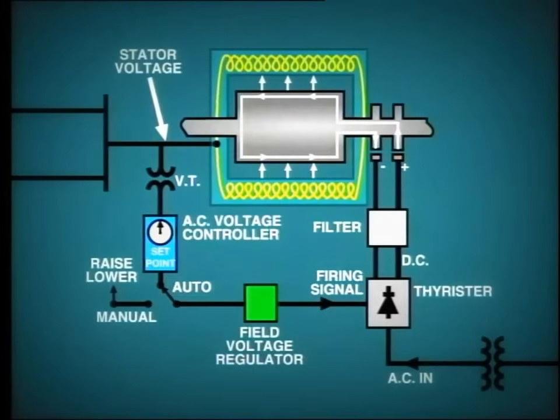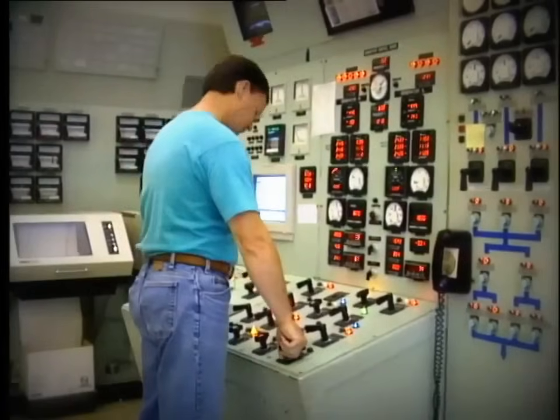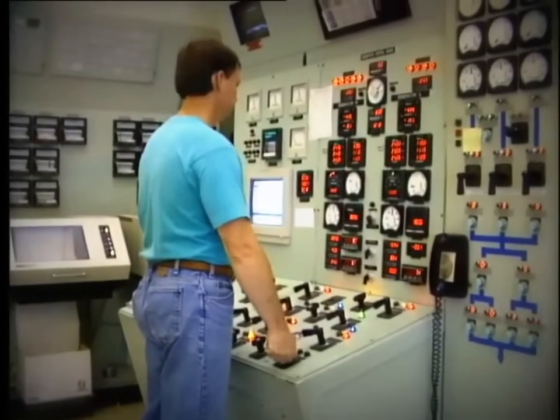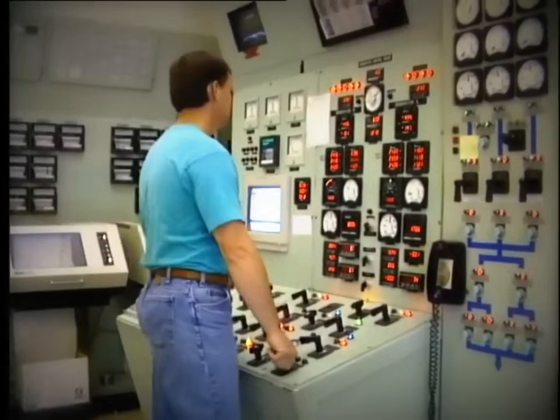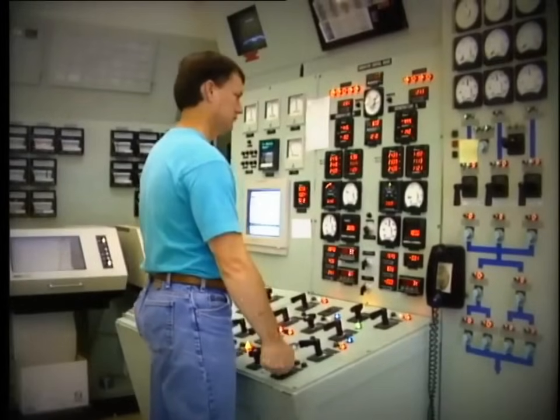That is from the AC voltage controller. This controller monitors the generator bus output voltage through VTs and automatically adjusts excitation to maintain the set point voltage. The operator can adjust this set point and thus exercise control while the excitation system is operating in auto.